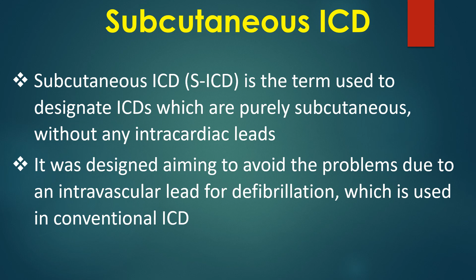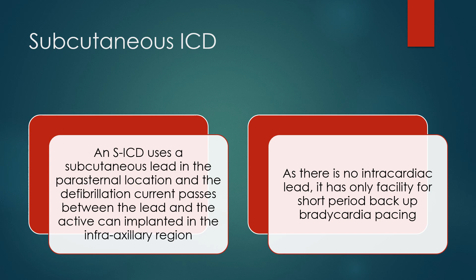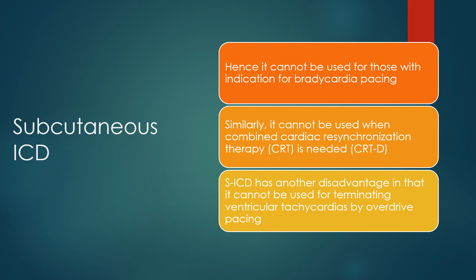An SICD uses a subcutaneous lead in the parasternal location, and the defibrillation current passes between the lead and the active can implanted in the infraaxillary region. As there is no intracardiac lead, it has only facility for short period backup bradycardia pacing. Hence, it cannot be used for those with indication for bradycardia pacing. Similarly, it cannot be used when combined cardiac resynchronization therapy is needed. SICD has another disadvantage in that it cannot be used for terminating ventricular tachycardias by overdrive pacing.